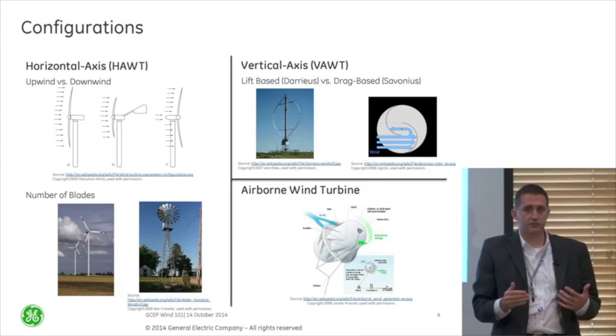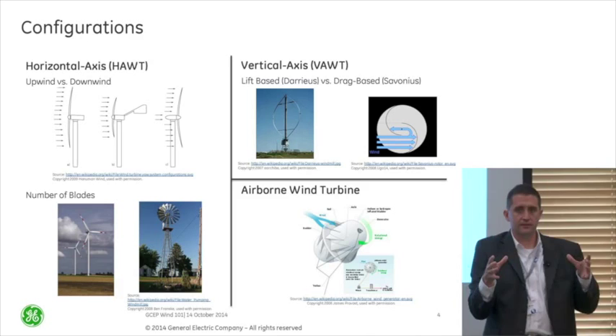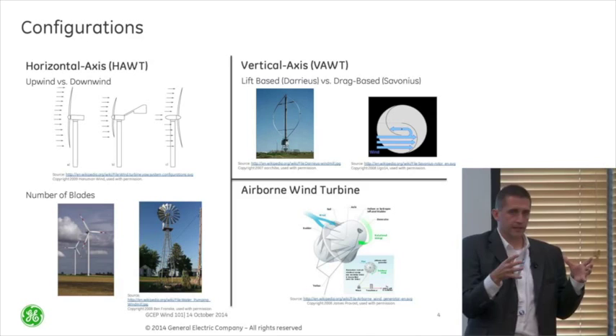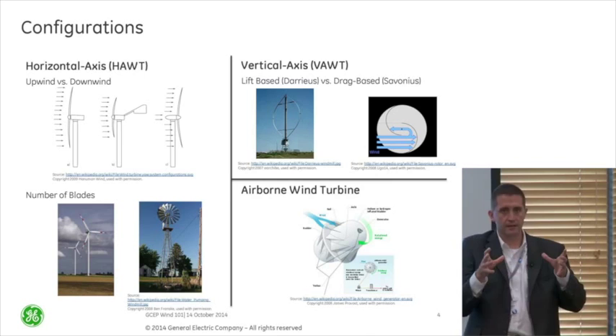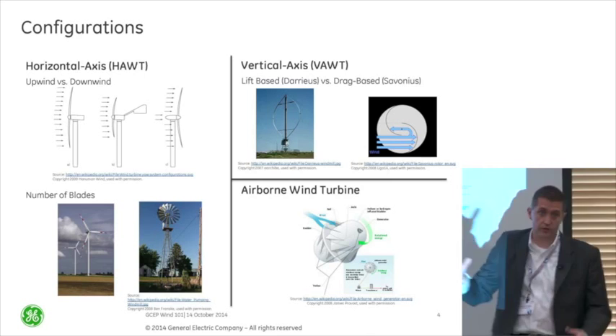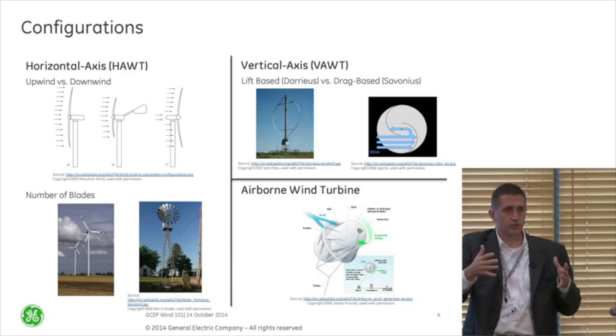To make sure it's facing the wind, upwind turbines have what they call active yaw — they have a mechanical ability and sensor so they can point themselves into the wind based on control algorithms. You can also do a passive yaw, where you have some sort of tail or vane on the back to automatically align you into the wind. You see that more often in small scale turbines because it would be a bigger cost on large scale.